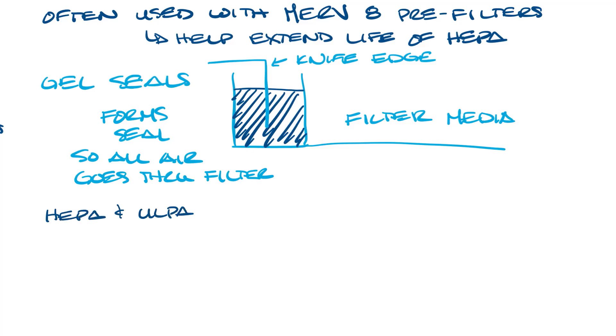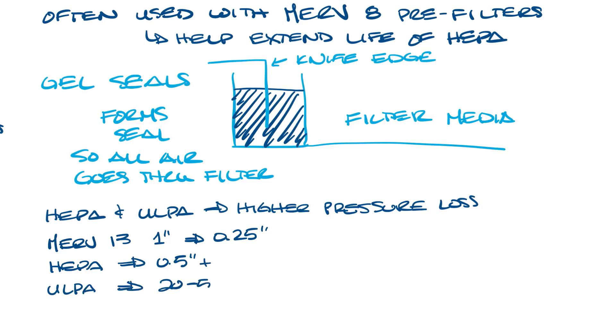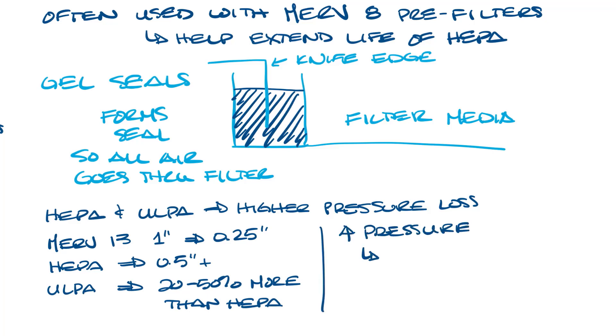One challenge to using HEPA and ULPA filters is that they have a high static pressure drop. A standard 1-inch MERV 13 filter will have a pressure drop of about a quarter inch. HEPA filters could have about a half inch or more depending on airflow, and ULPA filters would be an additional 20 to 50% more than the HEPA filter. This means you need higher pressure in your HVAC system to overcome the pressure loss through the filter.